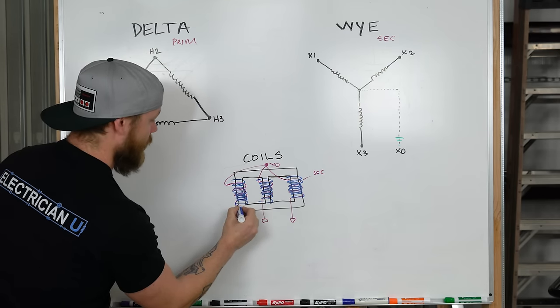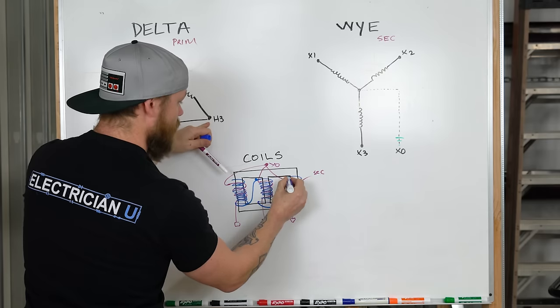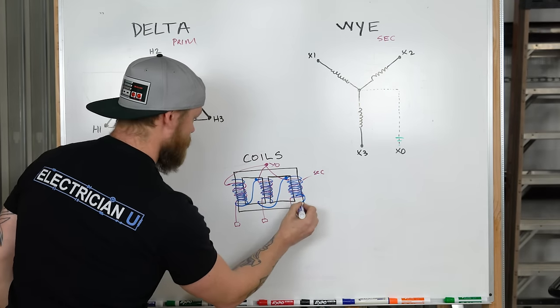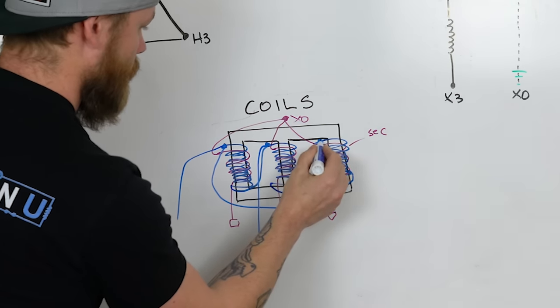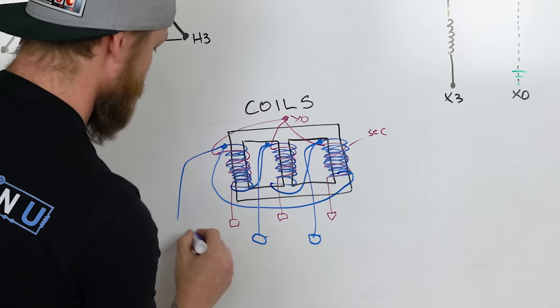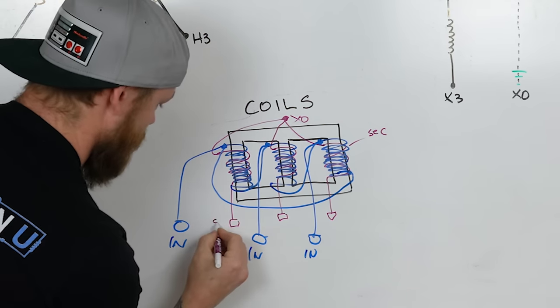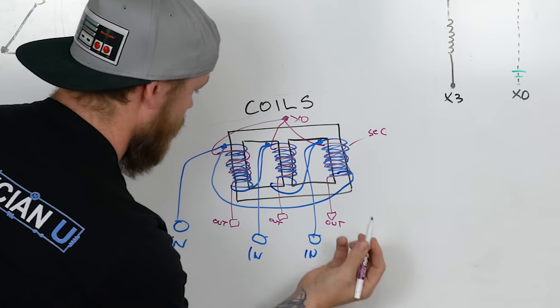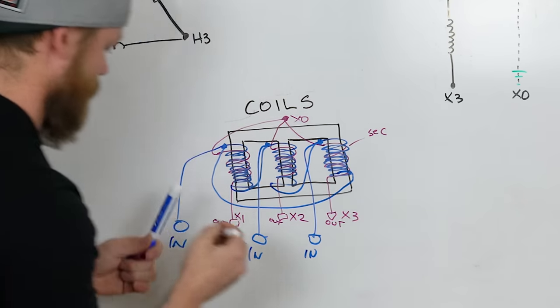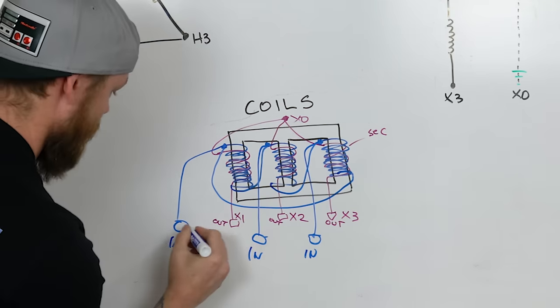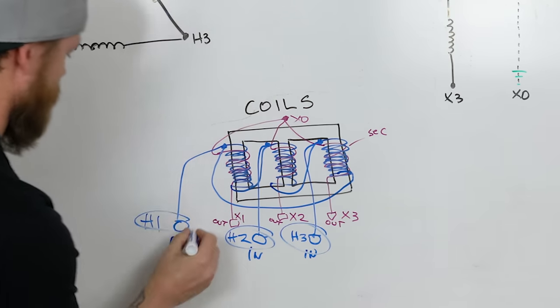H2 connects to H3, and H3 goes back to H1 — forming a triangle. At each one of those junction points there's a terminal that comes out, and those are where you put your high voltage in. So those would be your H1, H2, H3 inputs, while X1, X2, X3, and X0 are your outputs. That's how they're wound: twice as much on the primary, half as much on the secondary — that's how you get a two-to-one turns ratio. There are four-to-one ratios and many others as well.